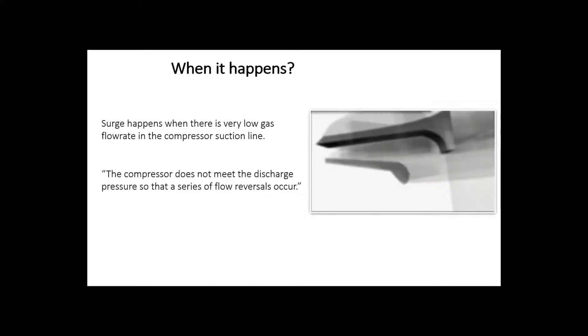Surge happens when we have very low gas flow rate in the compressor suction line. This minimum gas flow does not fill the impellers fully, so the compressor is not able to displace the amount of gas trapped inside. The flow, instead of going to discharge piping, experiences reversals and goes back to fill the empty impellers. Again, the compressor tries to deliver it to discharge line and the same process repeats itself.